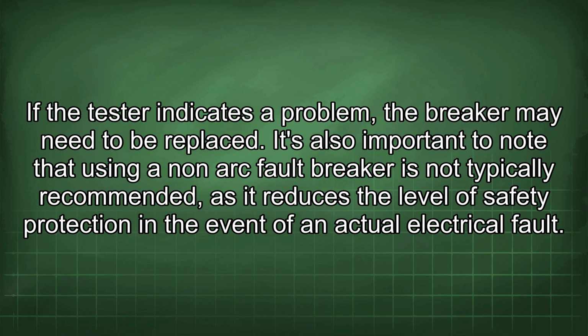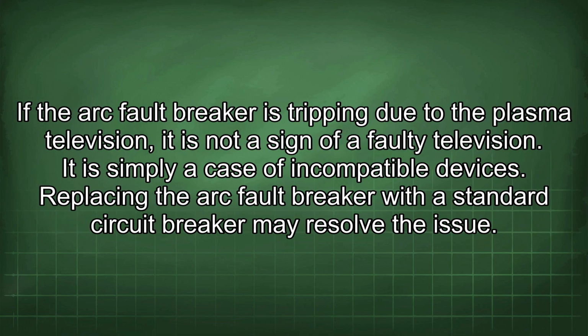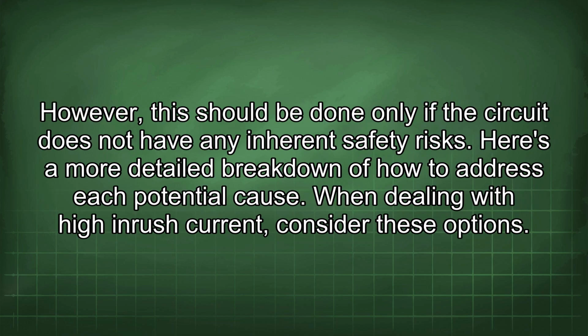It's also important to note that using a non-arc fault breaker is not typically recommended, as it reduces the level of safety protection in the event of an actual electrical fault. If the arc fault breaker is tripping due to the plasma television, it is not a sign of a faulty television. It is simply a case of incompatible devices. Replacing the arc fault breaker with a standard circuit breaker may resolve the issue. However, this should be done only if the circuit does not have any inherent safety risks.